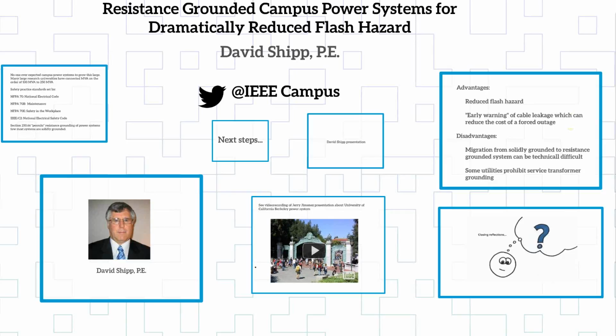That's the consequences of what can happen with the solidly grounded systems, and in their case, they lost their battery supply to compound it, so there's nothing that could trip. But the point is there's horrendous amounts of energy there at the 15 kV. It's the backbone of your entire power system. You lose your 15 kV distribution system or substation feeding your campus, you're dead. You may have a few emergency generators to go, but it's literally the electrical backbone of your facility.